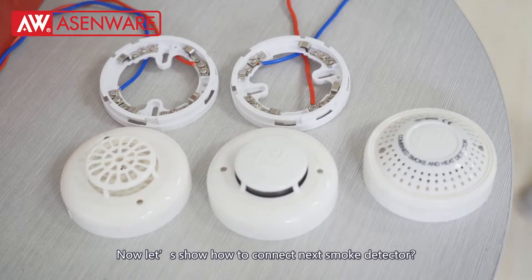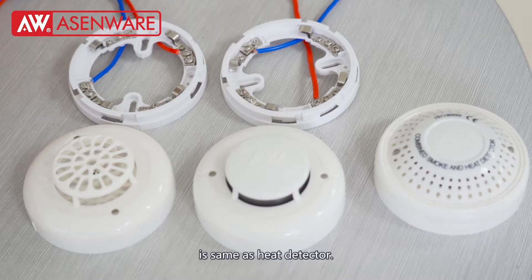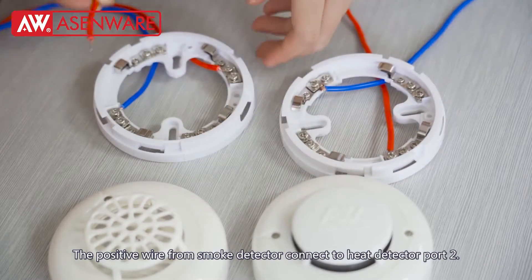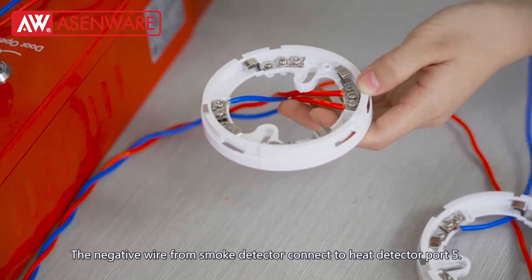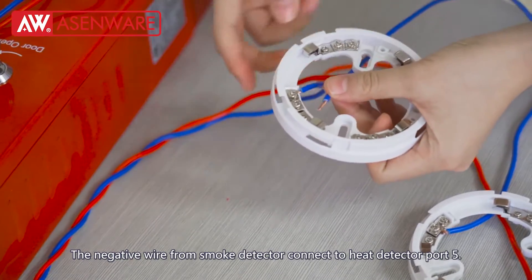Now, let's show how to connect the next smoke detector. The smoke detector and the combined detector wiring is the same as the heat detector. The positive wire from the smoke detector connects to heat detector port 2. The negative wire from the smoke detector connects to heat detector port 5.